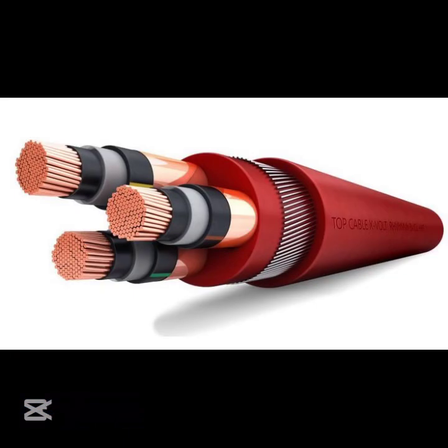Number 7. Use of shielded cables. Shielded or underground cables reduce the risk of direct lightning strikes on power lines. The shielding layer in these cables provides a path for the lightning current to flow safely to the ground, protecting the internal conductors. Underground cables are further protected by their burial depth and surrounding earth, which provides additional insulation against lightning strikes.